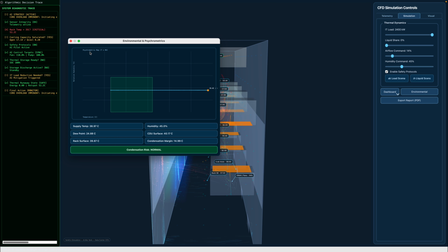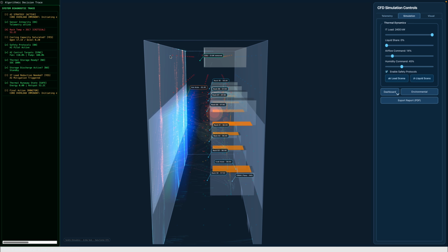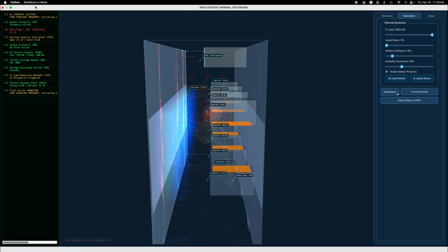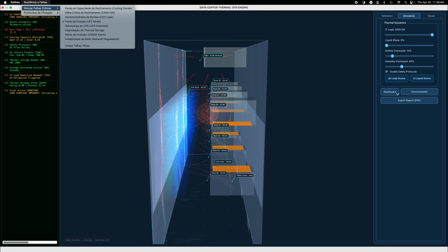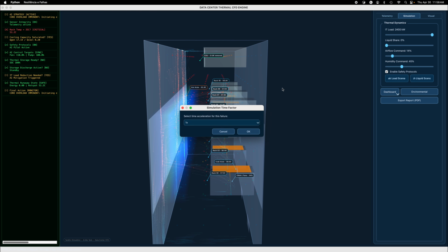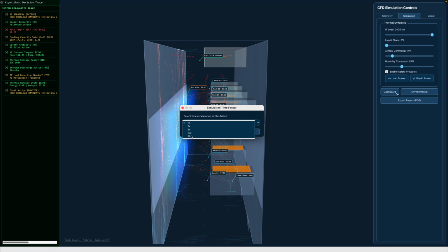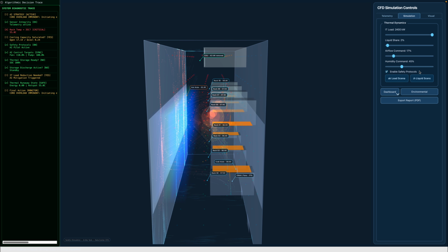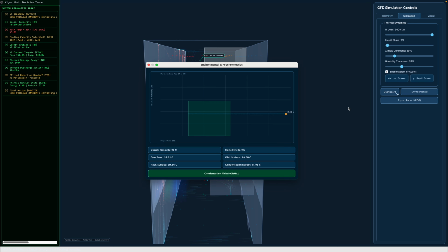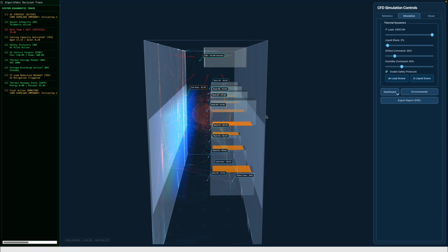It's basically like cruise control in a car. It doesn't just blindly slam on the gas or the brakes. Yeah. It calculates how fast you are approaching your target speed so you don't overshoot it. Right, because in a server room, overshooting the cooling causes condensation, while undershooting obviously causes a fire. To support that delicate balancing act, the code also runs an incident analyst script. Which does what exactly? It takes raw telemetry, so thousands of temperature data points, and transforms them into structured semantic context. That way, a large language model, like Gemini, can process the technical reports.